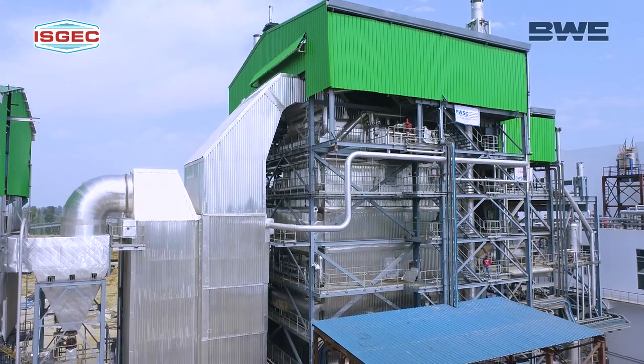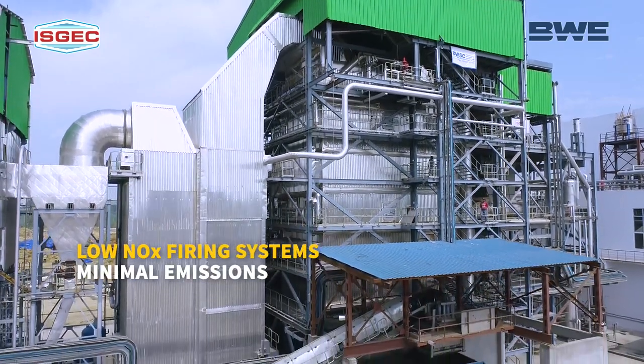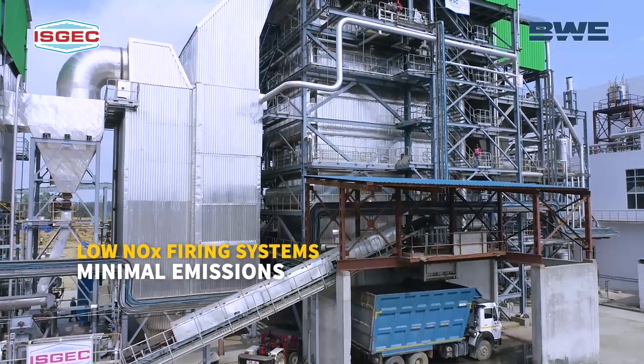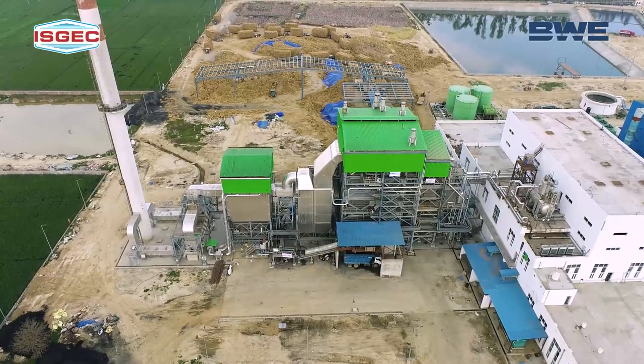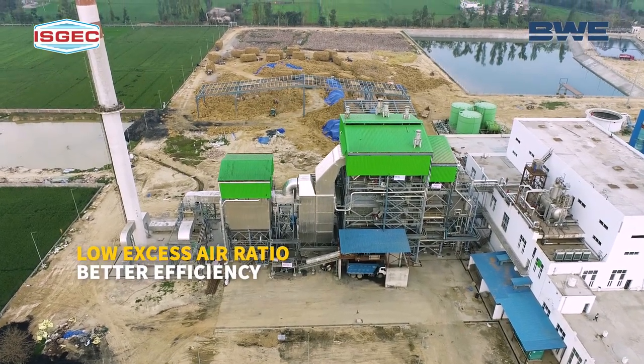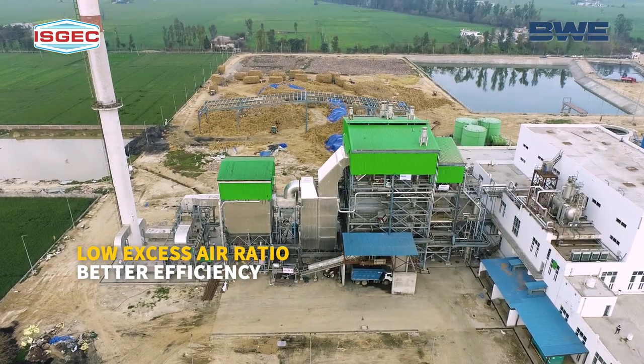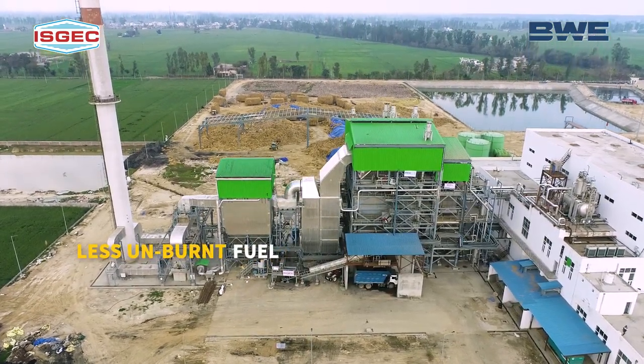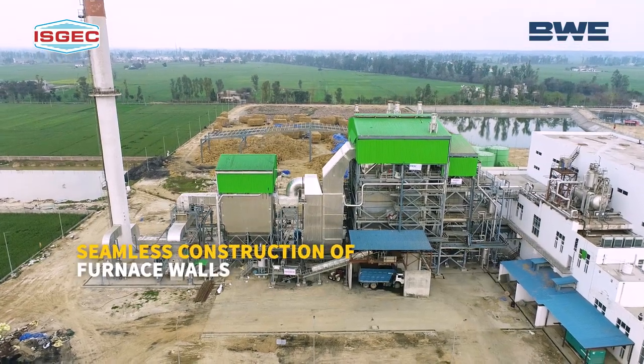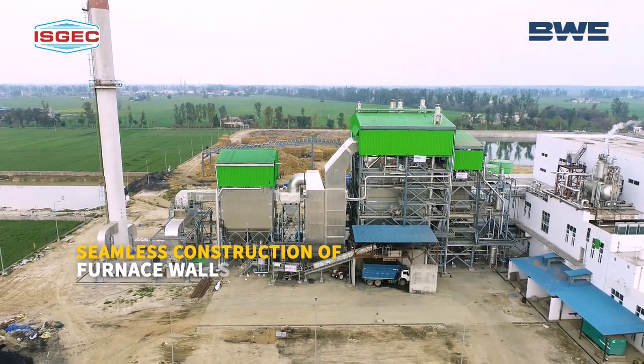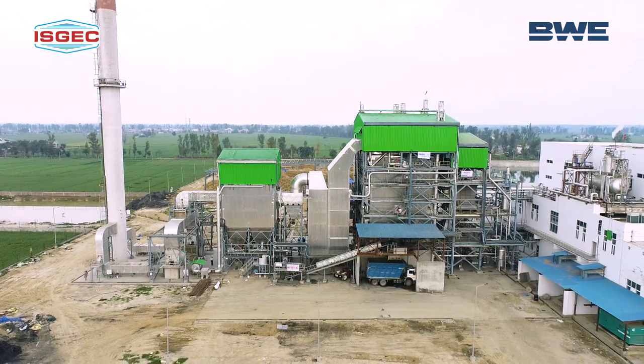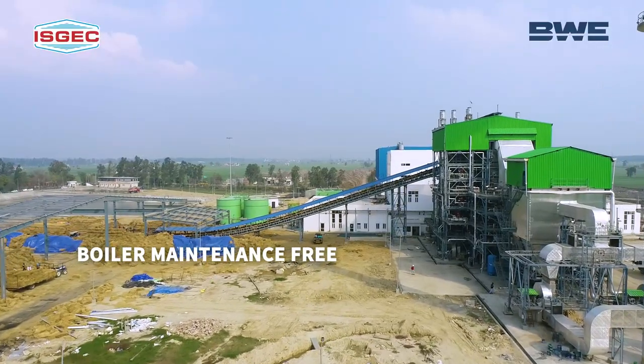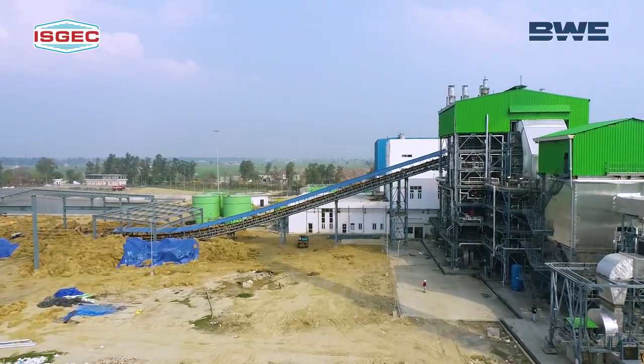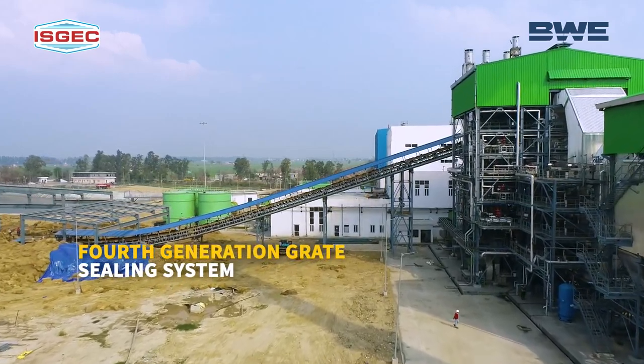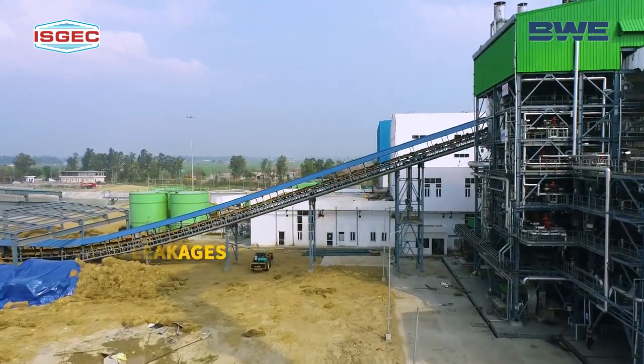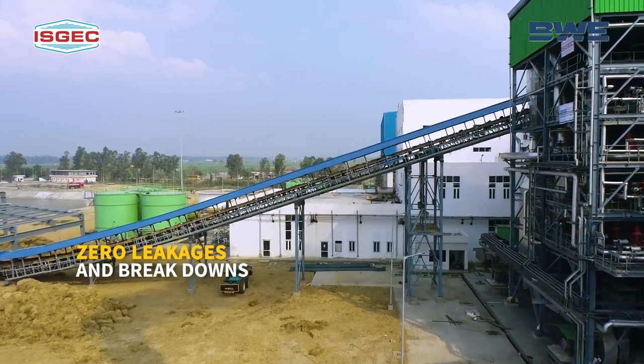Other advantages are low NOx firing system, ensuring minimal emissions, low excess air ratio, ensuring better efficiency and less unburnt fuel, seamless construction of furnace walls, side walls and top ceiling, ensuring a longer life for the boiler walls, making the boiler maintenance free. Fourth generation grate sealing system, ensuring zero leakages and breakdowns.